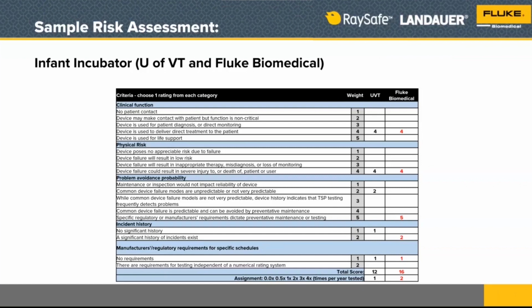We, however, have a little bit different opinion. We think that the infant incubator is a more risky environment based on the number of incidents per year that occur and the importance of making sure that this is safe and effective for clinical use. We come up with a total risk score of 16, which clearly satisfies the requirements for doing tests twice per year. So for some of you, you're going to say, well, Jerry, that's fine.